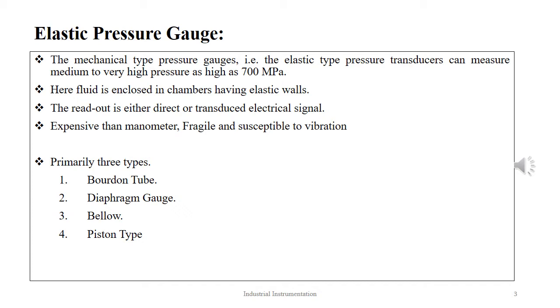The elastic transducers are costlier than their manometer counterparts and they are fragile and susceptible to system vibrations. There are mainly three types of elastic pressure transducers and a fourth one. They are Bourdon tube, diaphragm gauge, bellow, and the fourth type is piston type.